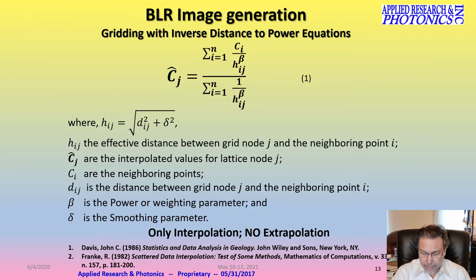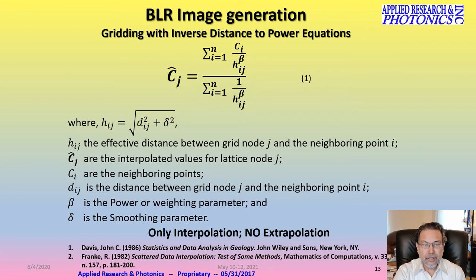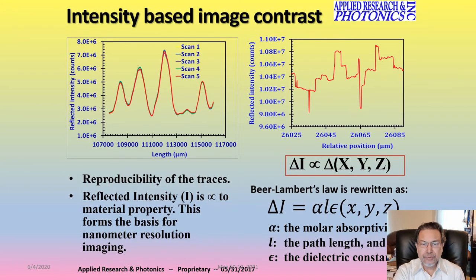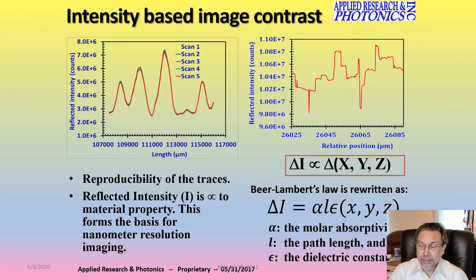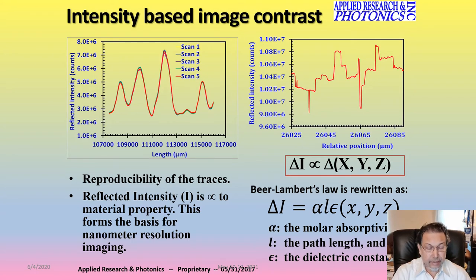The algorithm we use is what we call an inverse distance to power equation, used to generate the images. Two things are important: if we scan the same feature over and over again, we should get the same profile. We can rewrite the Beer-Lambert law in terms of intensity because the reflected intensity is material dependent, which lets us discriminate between materials and provides contrast generation from which the image is formed.